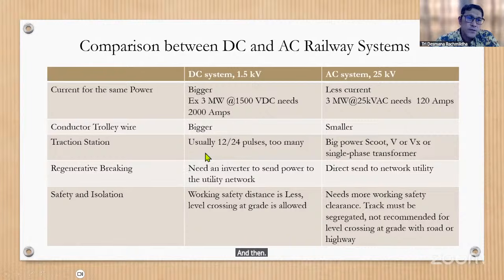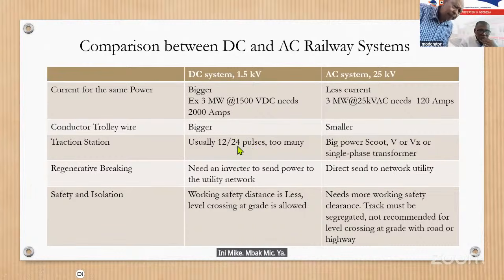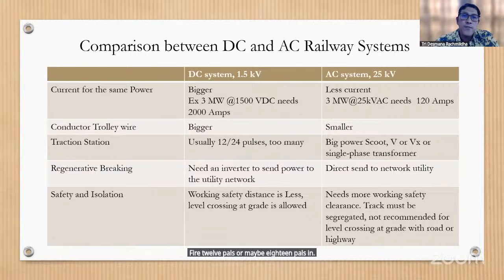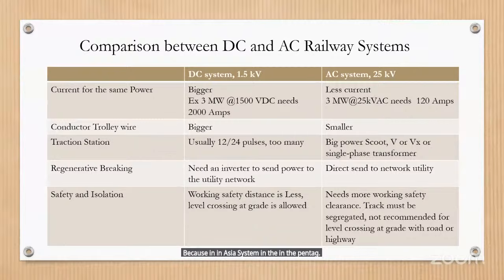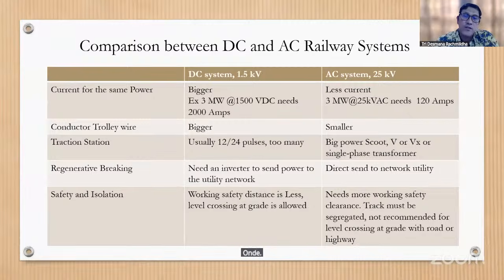And then for the traction station, especially the transformer in the DC system, we use 12 pulse or maybe 18 pulse, in a more complicated system. As for the AC system, we require the Scott transformer or V or VX single phase transformer with the objective to balance the three phase, because in the AC system the pantograph of the train is connected only to one phase of the catenary system, right? So to balance this unbalanced effect from the pantograph, we can use the Scott transformer or V or VX single phase transformer.